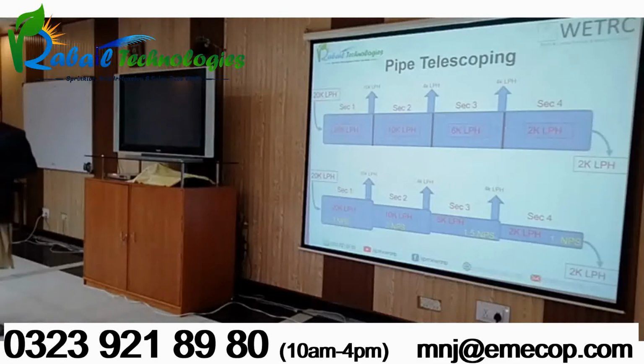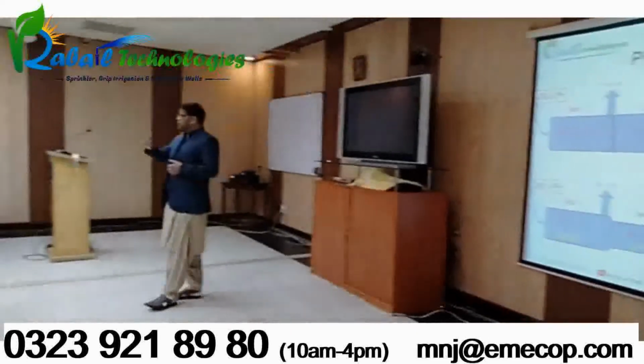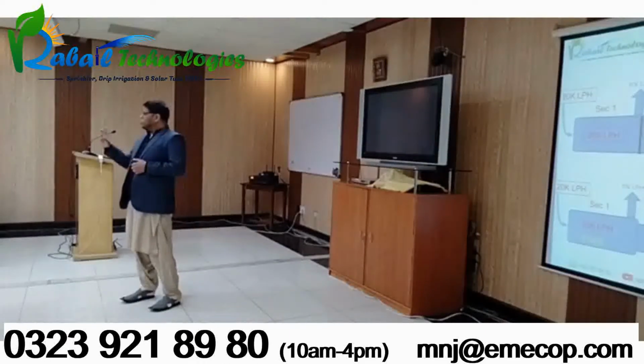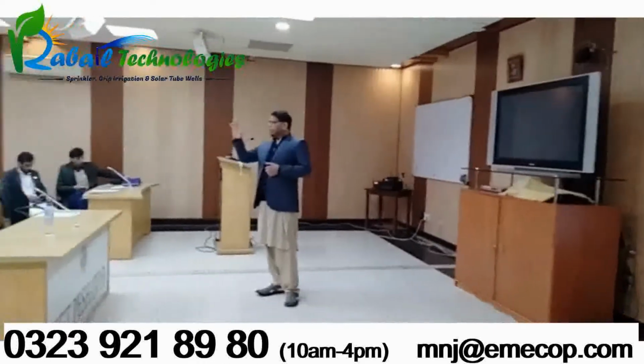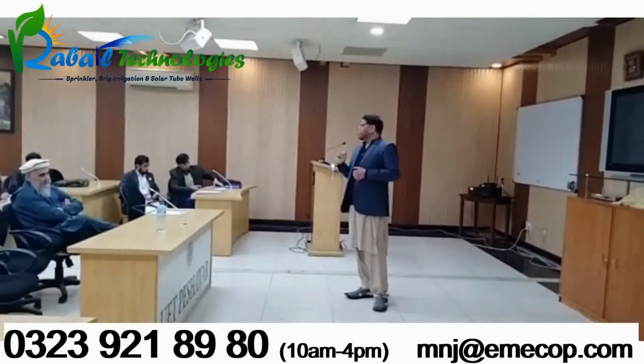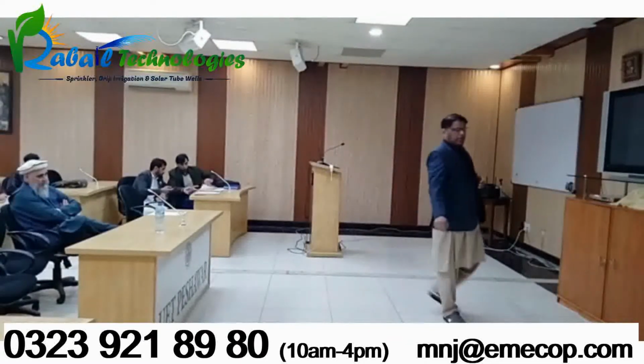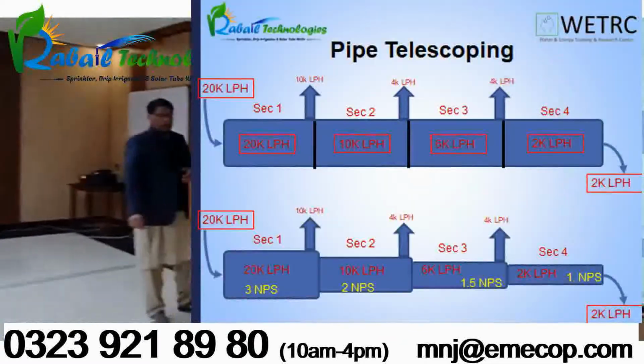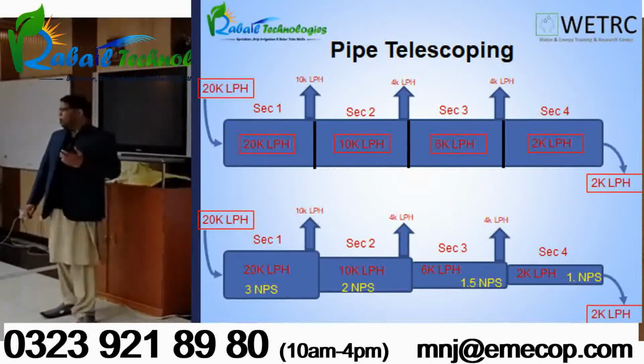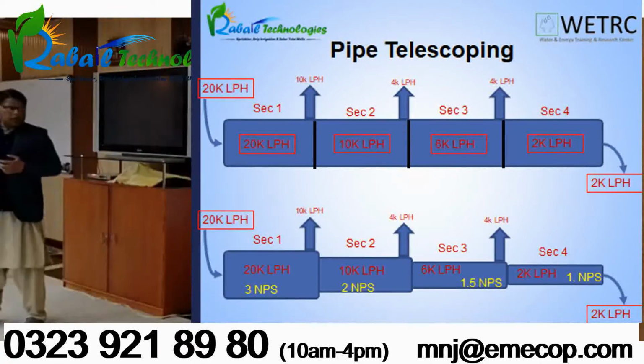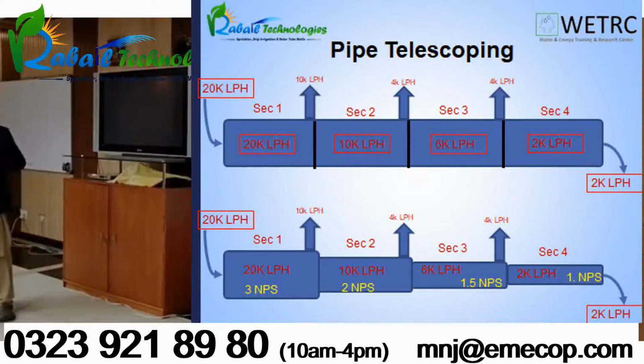you put the velocity of 1.5 meter per second, the flow rate of 2,000 liter per hour, so you will get the cross section area, and from that you will get the diameter of the pipe. Based on my experience, I knew it will be 1 nominal pipe size, that is 1 inch nominal pipe size diameter. So for section 4, I will design 1 inch pipe size.